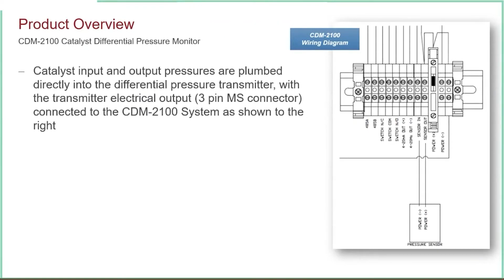The catalyst input and output pressures are plumbed directly to the DP transducer, and it has a 3-pin military connector on the side of it. That's something we put in there to make life easy. Those cables are 5, 10, and 30 feet, and plug right in with a 3-pin military connector, and then you hook 2 wires up here on the right-hand side. You can see where the sensor in and sensor out connections are. Other than the power connections, you're pretty much good to go. So this is a fairly easy installation to do.